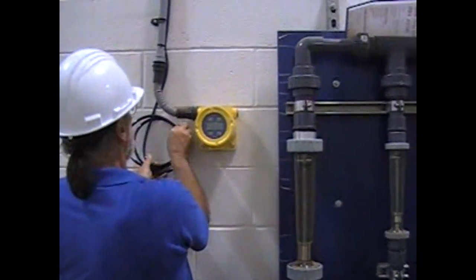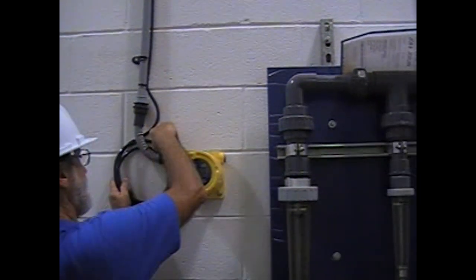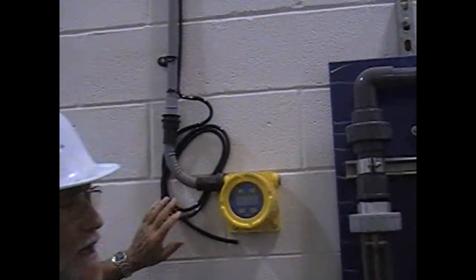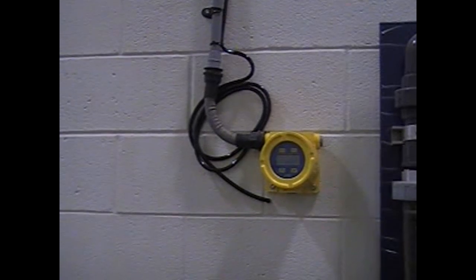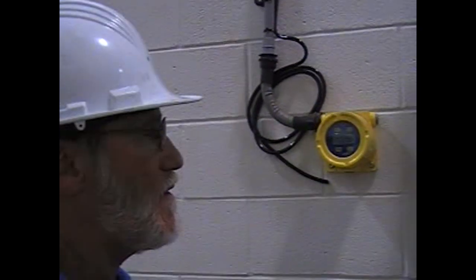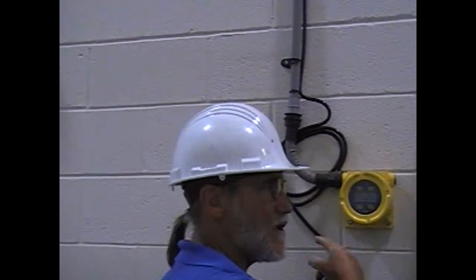What this hose is for is your hydrogen test kit. And I'm sure that Emmett tested the hydrogen when he was here doing the programming. They'll send you two tanks in a small black suitcase. One tank is a blank, zero, to flush blow up against that sensor. The other one is 50% hydrogen. And you attach it to this here, and you start feeding hydrogen, so that the sensor sees hydrogen.